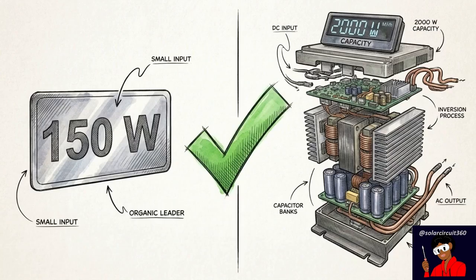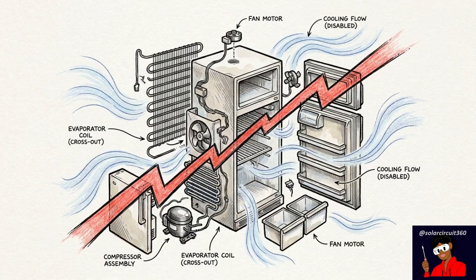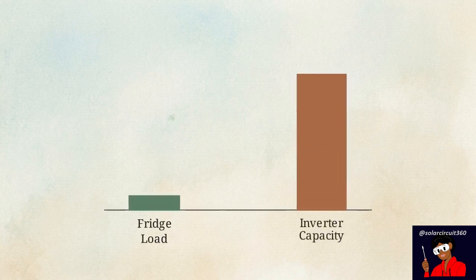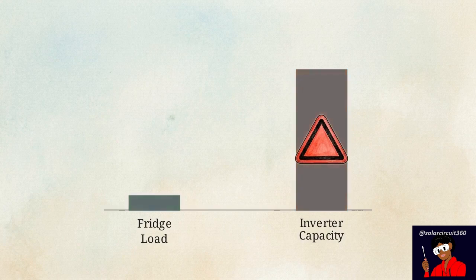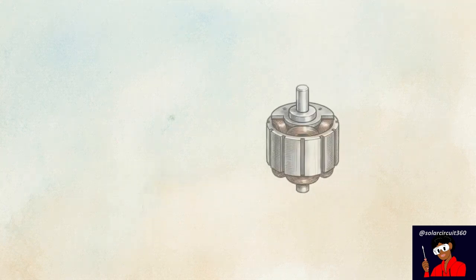Most system design guides focus strictly on the appliance nameplate. If the sticker says 150 running watts, standard industry logic dictates that a 2,000-watt inverter gives you plenty of headroom. But this shutdown has nothing to do with continuous power. Your inverter is not inherently too weak to run the fridge's normal cooling cycle. Even systems that are mathematically oversized by a factor of 10 still experience these sudden, hard lockouts, despite having a massive surplus of continuous power.